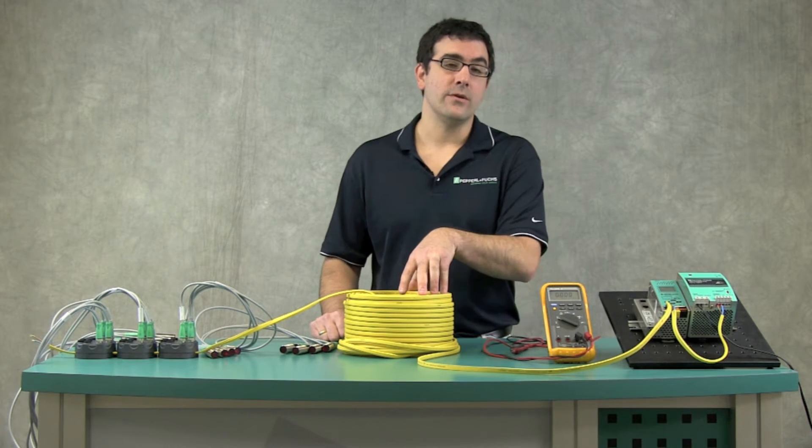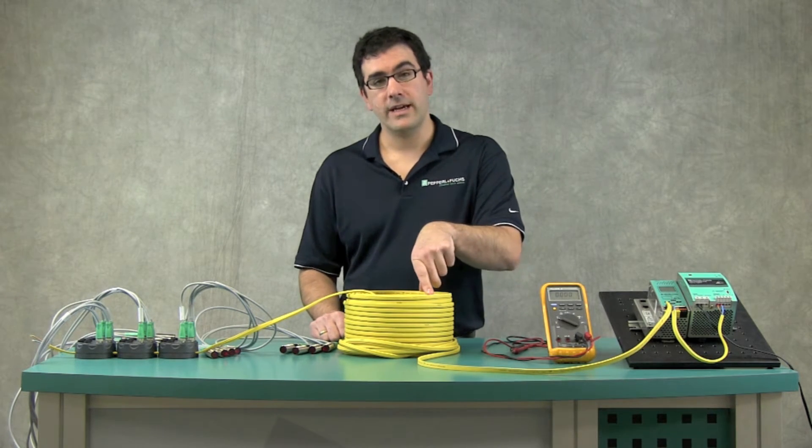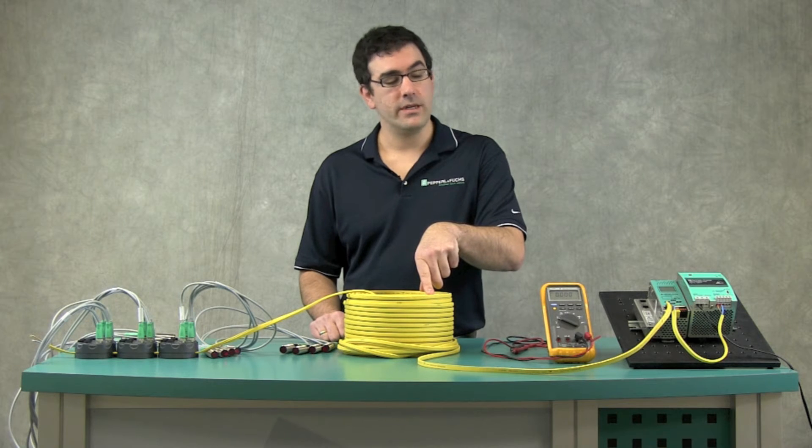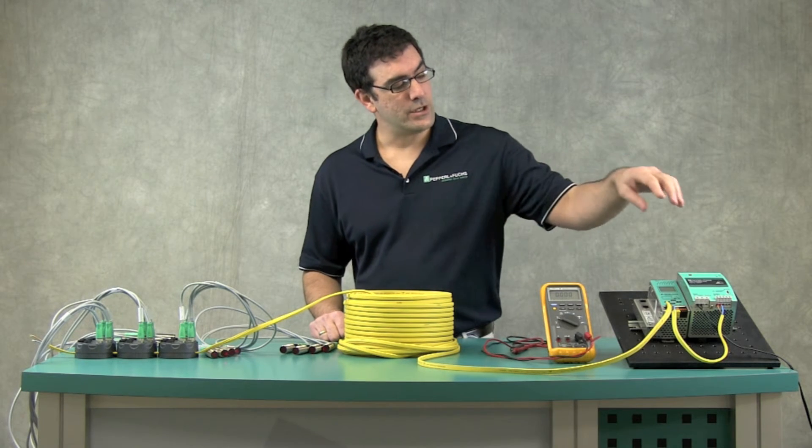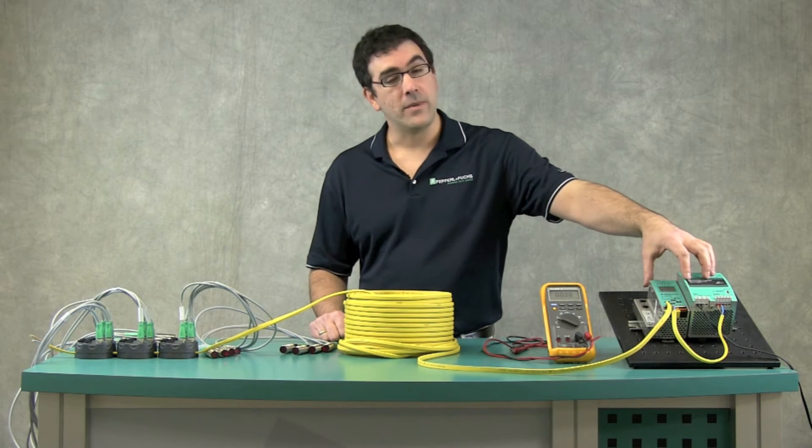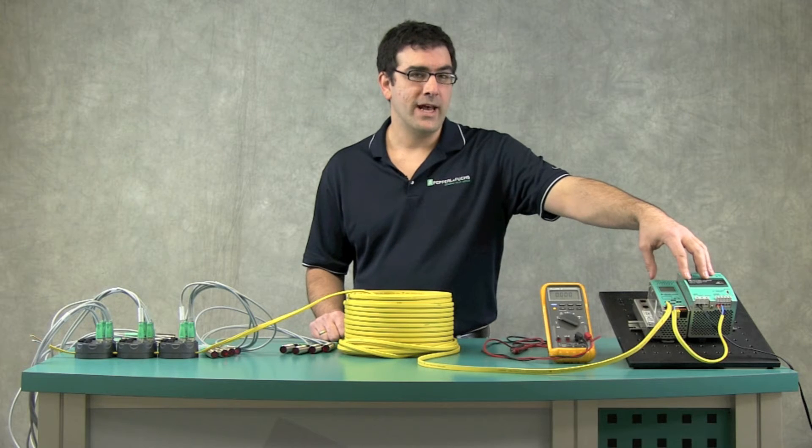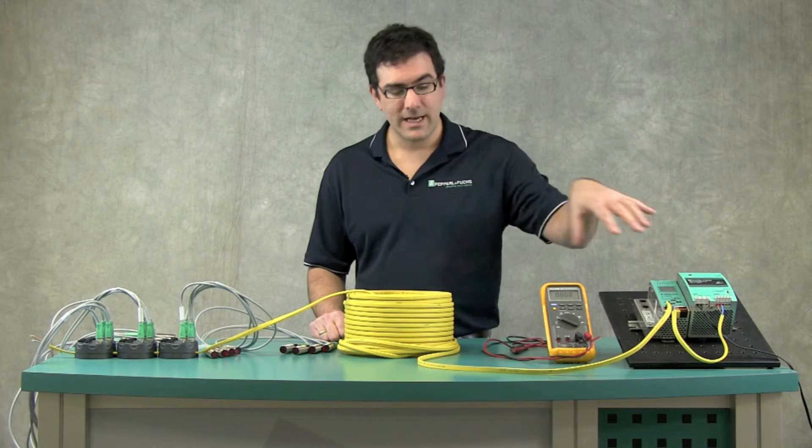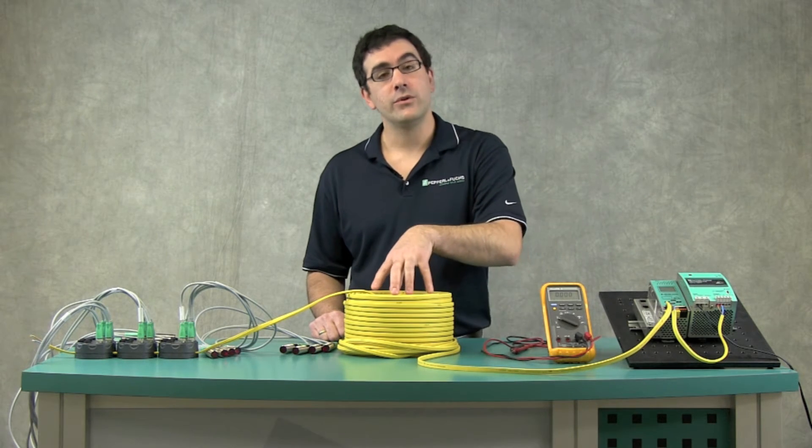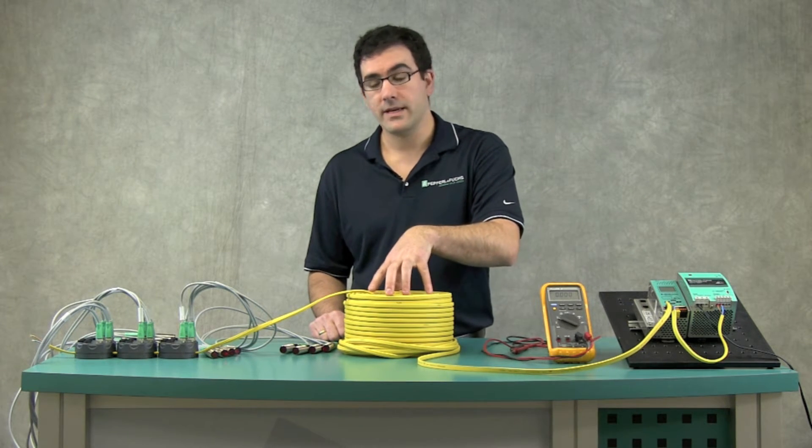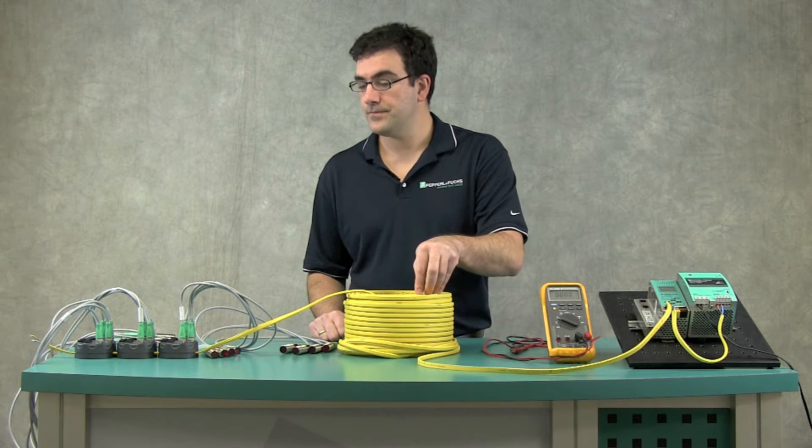ASI, which is an industrial bus, has power and communication on the same two conductors. We have a starting voltage on the power supply of about 30.5 volts. This compensates for any of the voltage drop on the cable due to the copper resistance.